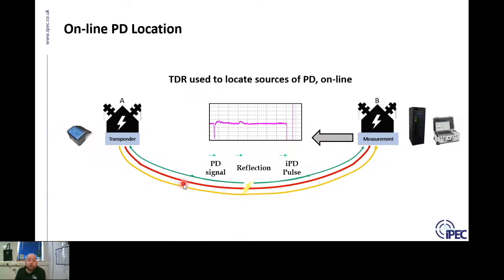Actually in this case, our transponder has a 10 microsecond delay so that it has enough time to process the data before sending the pulse, enough time to charge the capacitors before sending the pulse down the cable. The pulse is essentially like a PD reflection - the pulse is 500 volts, very large pulse, very high frequency, so very low in energy but very high voltage, so it's very clear to see at the other end of the cable. Now both of these units will automatically measure each one of these signals it receives, and it will receive hundreds per second.